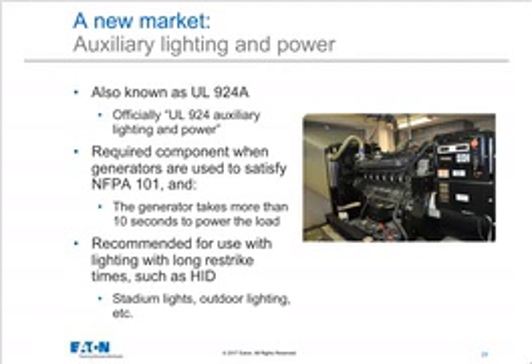But for most large buildings, they don't want to cycle the generator every time the utility power blinks. So the generator will have a 30-second or a couple of minute delay before it starts. In other words, the power has to be off and stay off for a period of time before the generator starts. So in that case, I need a UPS with just a few minutes of battery backup to keep the emergency lights operating until the generator comes on and takes over the long-term backup.